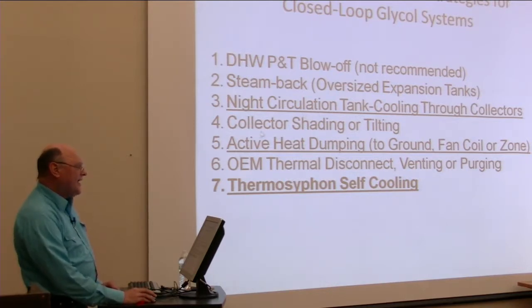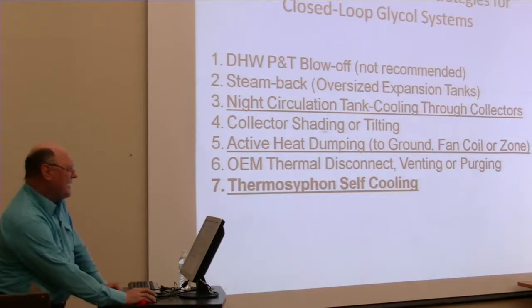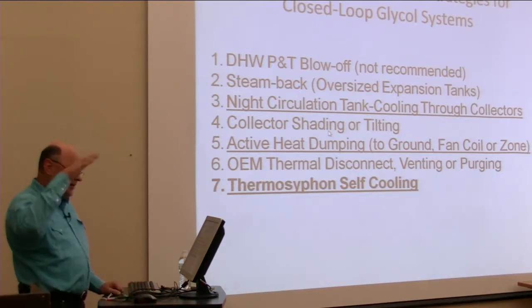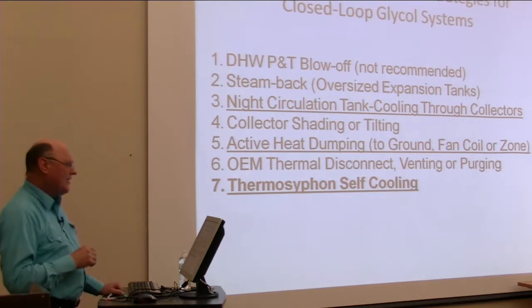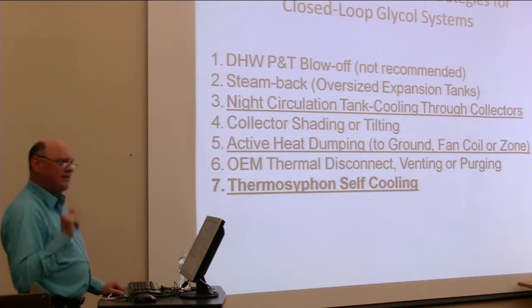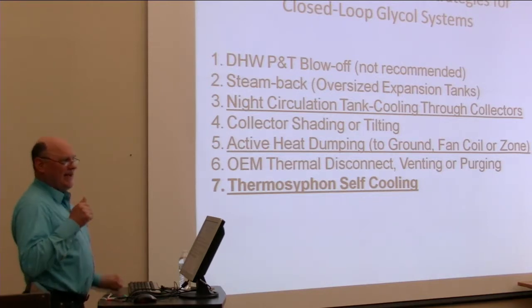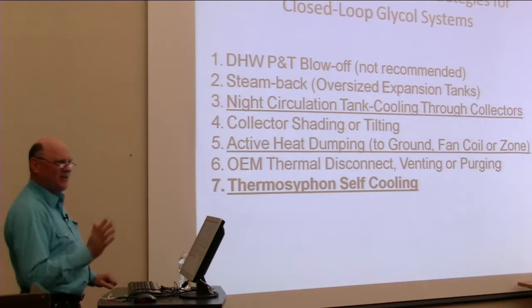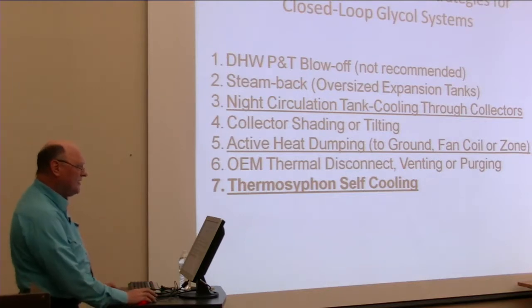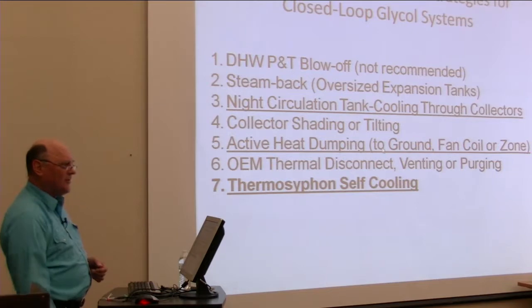Another way that system designers can design at the beginning of a project is shading or tilting. You can put an overhang that casts a shadow over the collector, or tilt the collector so that it doesn't face the summer sun. But that's something you can only do at the beginning, and you can only do it once. It's not something you can change after the collectors are installed, but it's good to think about when you're designing a system. Active heat dumping into the ground is used a lot by solar professionals, where the controller senses that the collectors are too hot, turns on the collector pump, and pumps the heat out and into an ice melt zone or into the floor of the garage, somewhere where it won't cause any trouble. That is used a lot, and that's built into our control system.